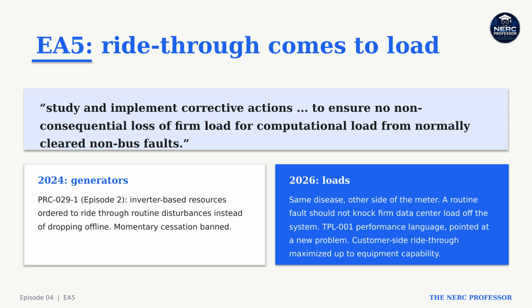Now, Action 5, the part of this alert nobody reads carefully enough. Transmission planners and planning coordinators working with transmission owners should study and fix the system side so that a normally cleared non-bus fault causes no non-consequential loss of firm load for computational load. Read that again. A routine fault should not knock firm data center load off the system. That is TPL1 performance language pointed at a brand new problem, and on the customer side, transmission owners should coordinate improvements that maximize the facility's ride-through up to what the equipment can take.